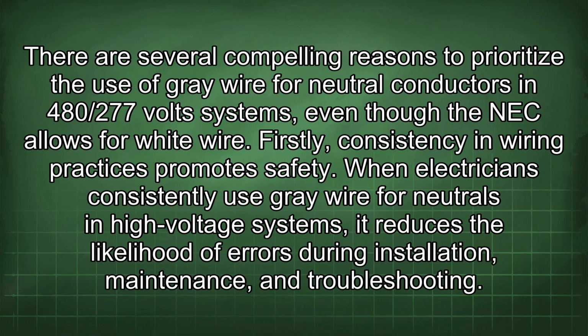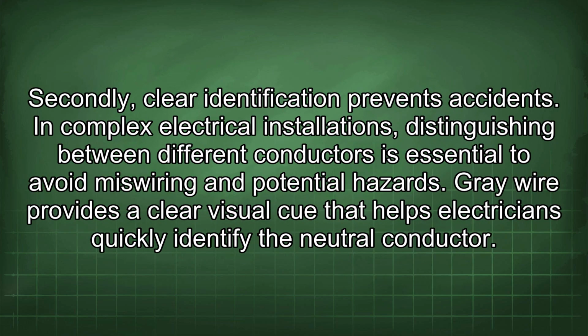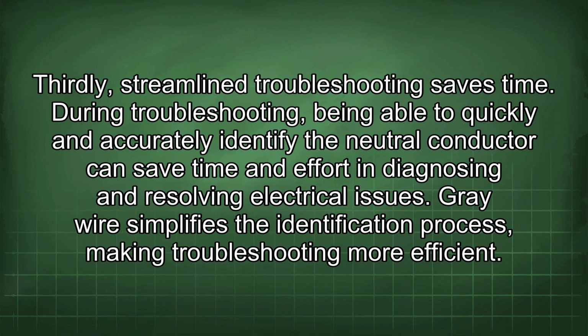There are several compelling reasons to prioritize the use of grey wire for neutral conductors in 480/277 volt systems, even though the NEC allows for white wire. Firstly, consistency in wiring practices promotes safety. When electricians consistently use grey wire for neutrals in high voltage systems, it reduces the likelihood of errors during installation, maintenance, and troubleshooting. Secondly, clear identification prevents accidents. In complex electrical installations, distinguishing between different conductors is essential to avoid miswiring and potential hazards. Grey wire provides a clear visual cue that helps electricians quickly identify the neutral conductor. Thirdly, streamlined troubleshooting saves time.